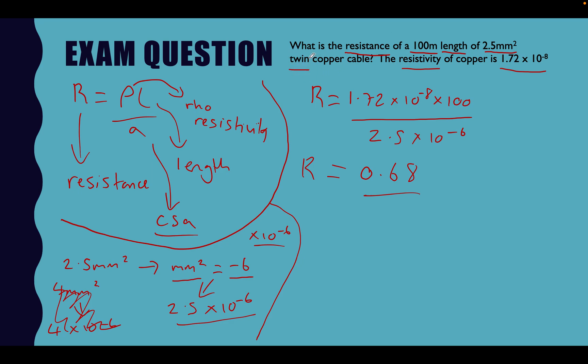This is a common mistake. The question specifies a twin copper cable — meaning there's a cable with two cores inside carrying the current. What we've calculated is the resistance for one length of cable. So we need to multiply 0.68 by 2 because we have a twin cable. That gives us 1.376 ohms, which is the resistance of a 100-meter twin copper cable with a CSA of 2.5 millimeters squared.